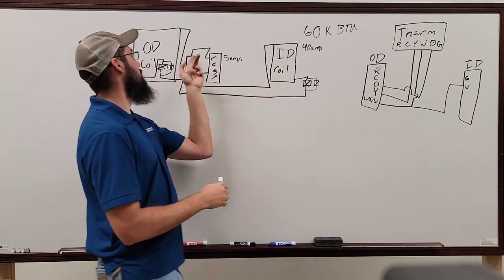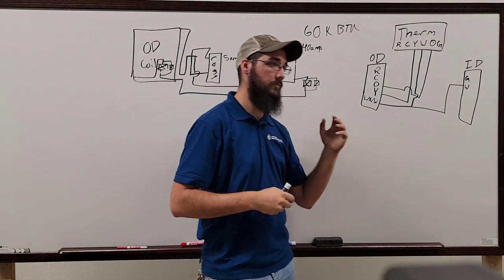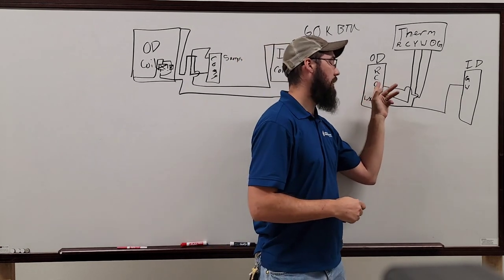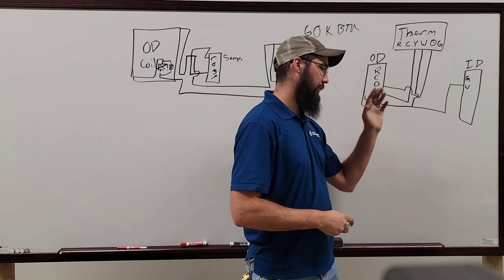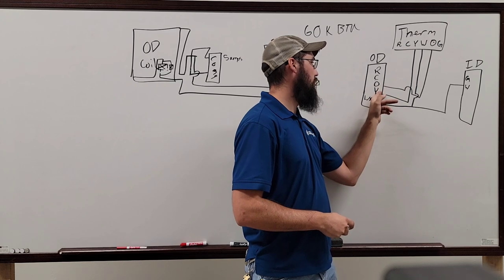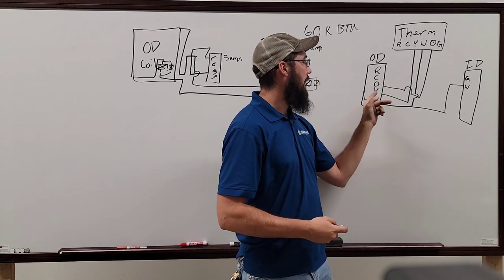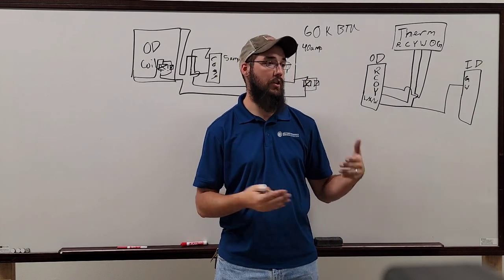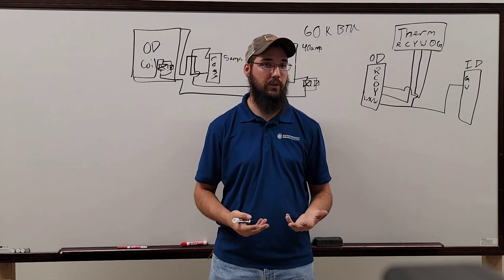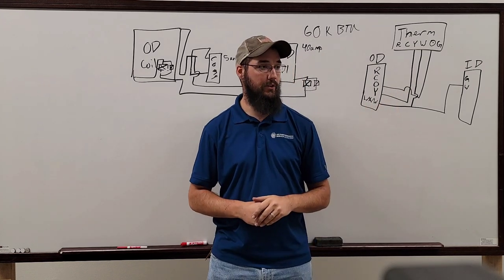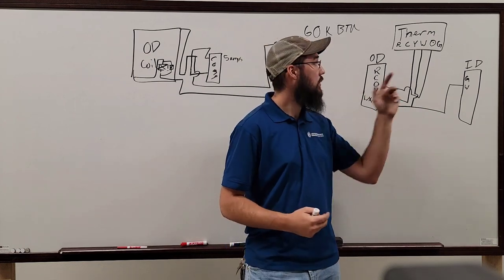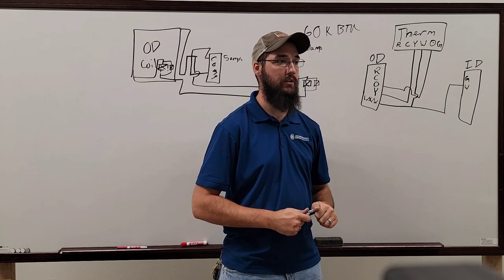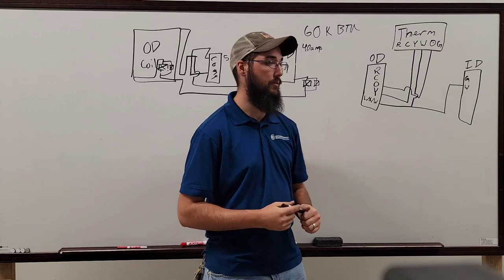So that coil is sitting right up here. It'll look like a little solenoid coil. Anyway. Sorry, I had trailed off for a second, coming back. So in heat mode, we're going to energize Y, and as long as parameters are sufficient, we will turn on and everything will go into a heating mode. And we will not be running the indoor heaters. This will be a stage one heat. W will not be energized at all at this stage. Okay? You have nothing on W.